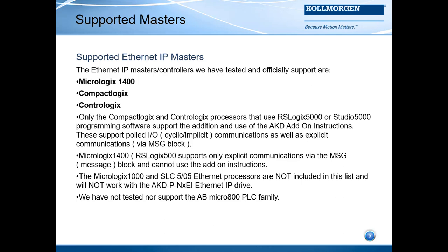The MicroLogix 1400, which uses RSLogix 500 for programming, supports only explicit communications via the MSG block and cannot use the add-on instructions. The MicroLogix 1000 and SLC 505 Ethernet processors are not included in this list and will not work with the AKD Ethernet IP drive. We have not tested nor support the Allen-Bradley Micro 800 PLC family.